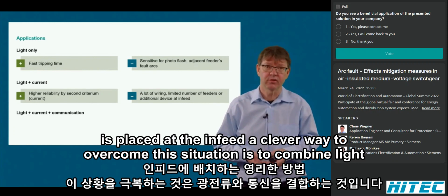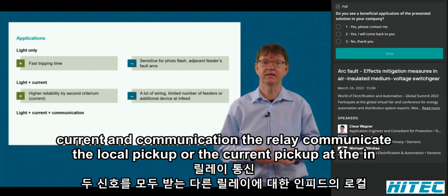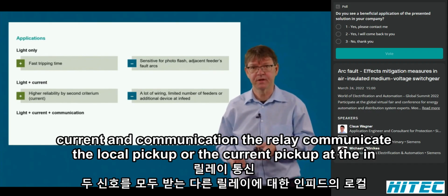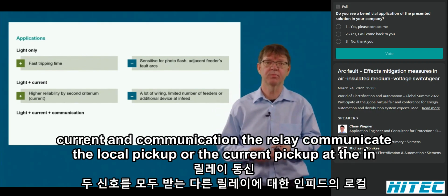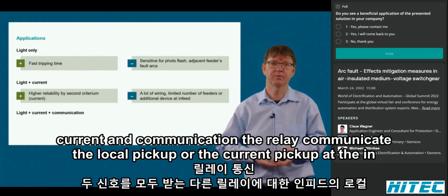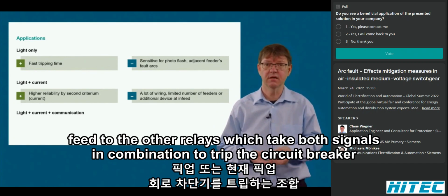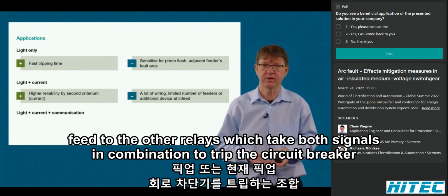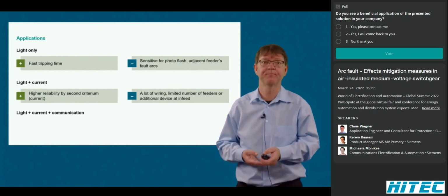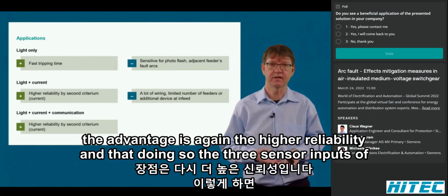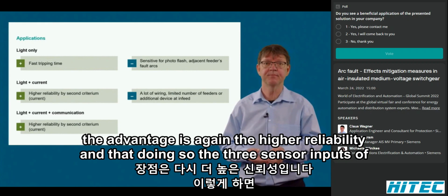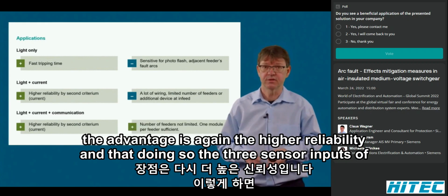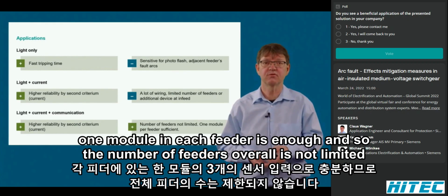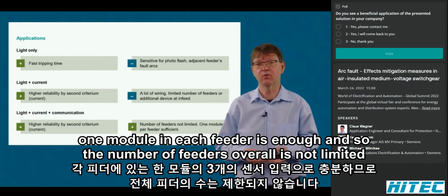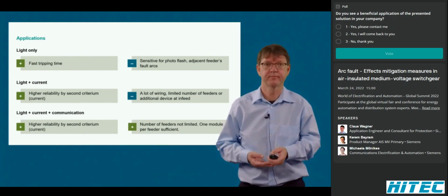A clever way to overcome this situation is to combine light, current, and communication. The relays communicate the local pickup or the current pickup at the in-feed to the other relays, which take both signals in combination to trip the circuit breaker. The advantage is again the higher reliability, and that doing so, the 3 sensor inputs of one module in each feeder is enough, and so the number of feeders overall is not limited.